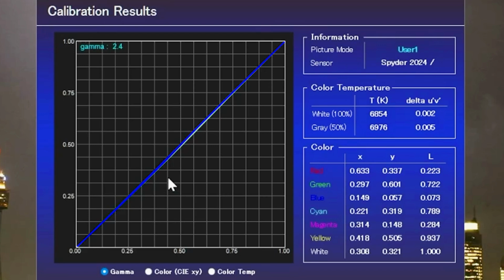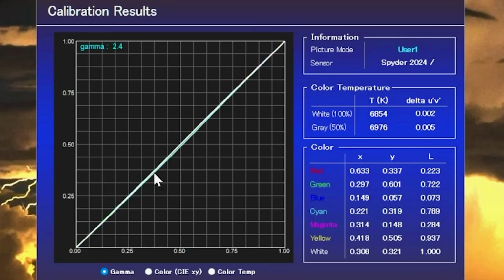if you look at the bottom here, the blue is before, the white is after, and the green is the 2.2 gamma curve, basically. It's going to be a straight line. So the after is the white here. We want this nice and straight, and you can see that it is. The green and the blue curves are underneath the white, right on the edge. But if you see a hump, typically what I've seen in most of the units is there might be a little bit of hump in the middle or something that's a little off from the factory. And so with the calibration, we really fine tune this gamma.